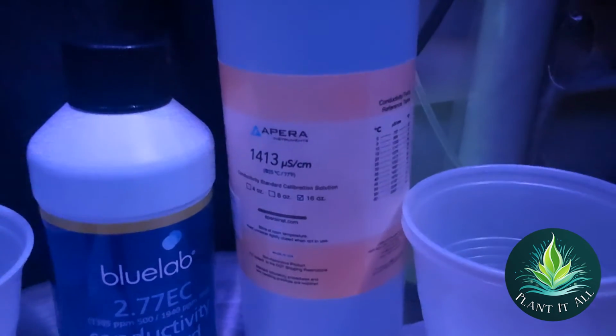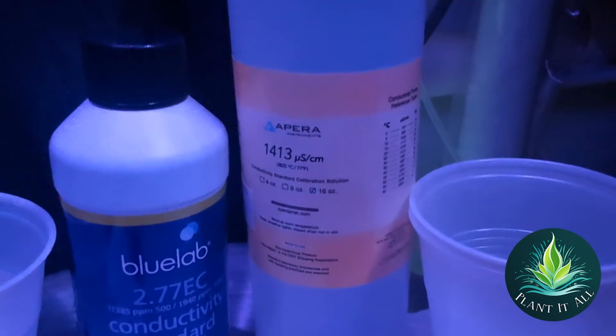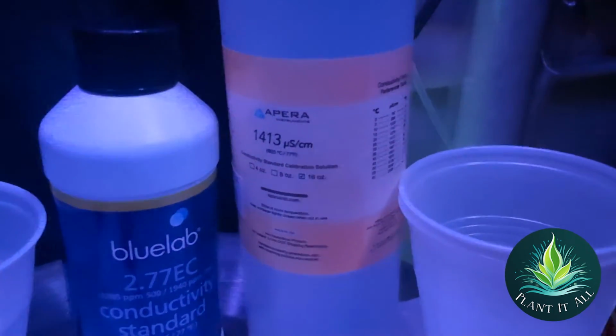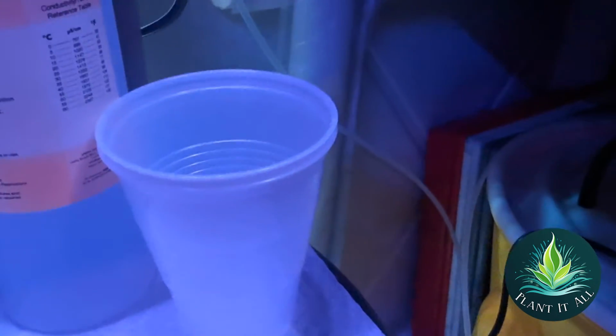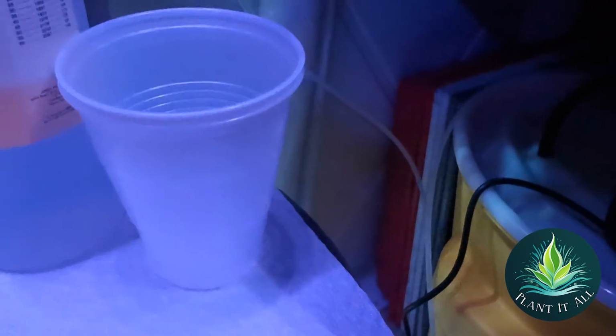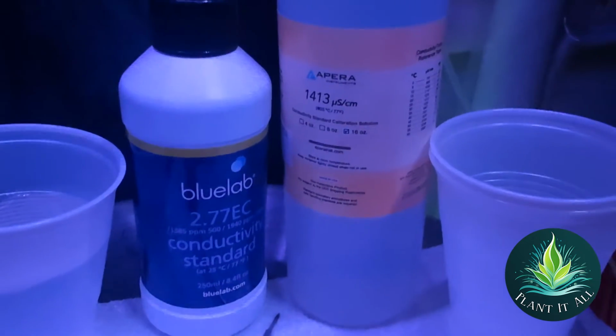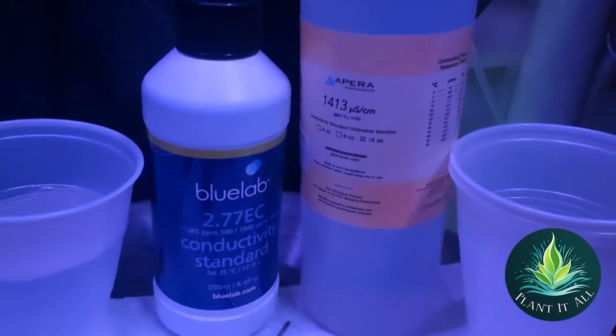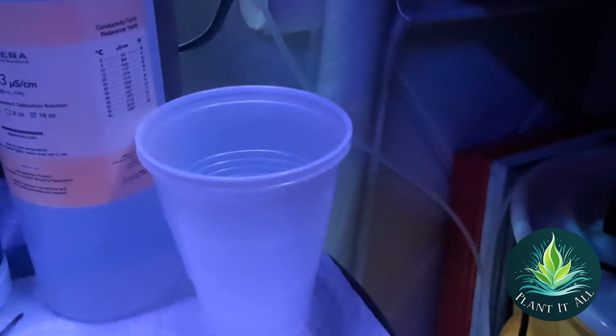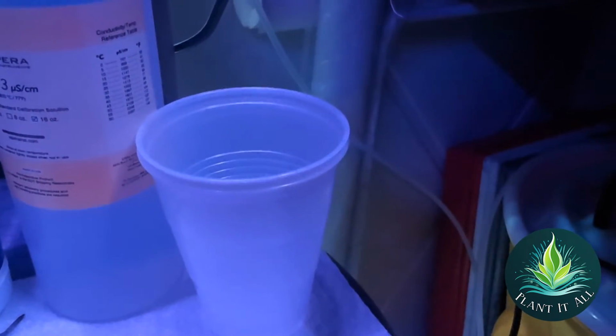All right, you got your solutions here. They should be right around 77 degrees now. Remember, that's important. And 2 additional clean containers. We don't want to be testing directly inside of our bottles, so we're going to pour off just enough to cover the tip of the probe entirely into a separate cup, and then put it in there for the calibration.